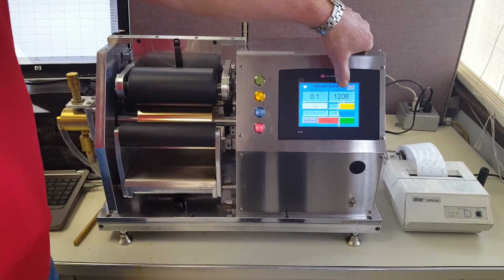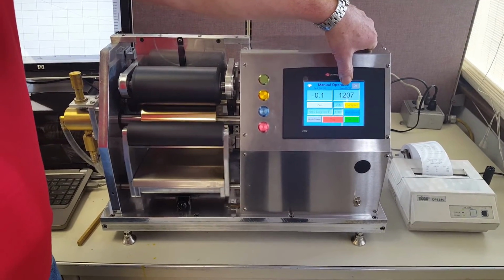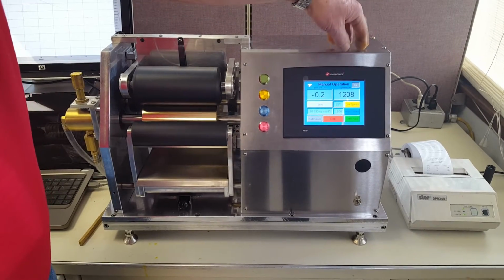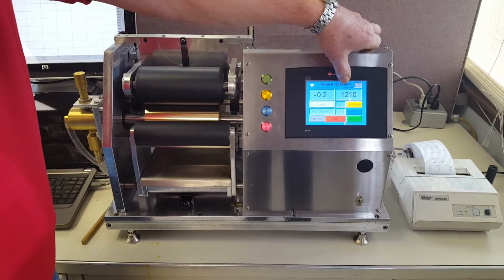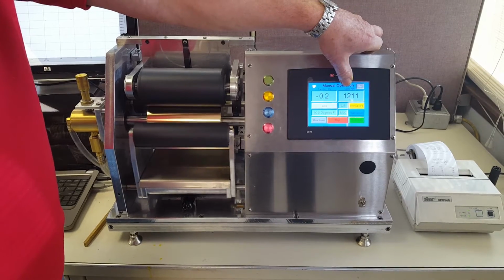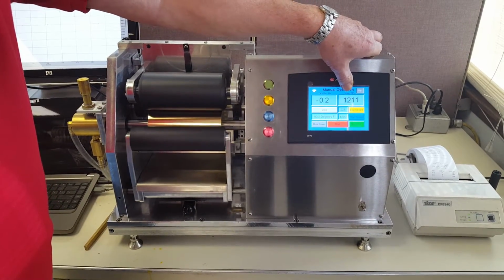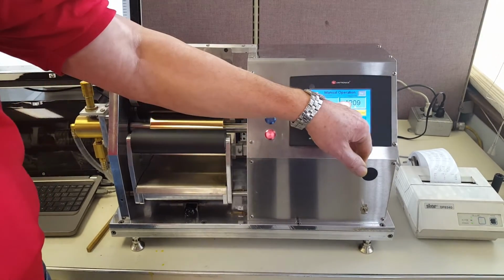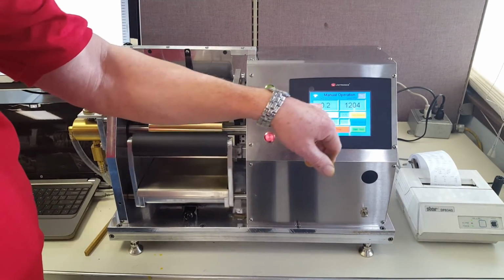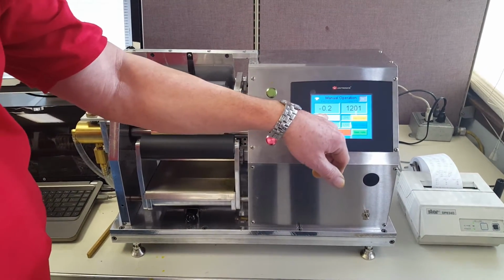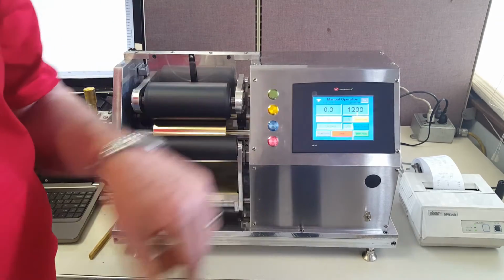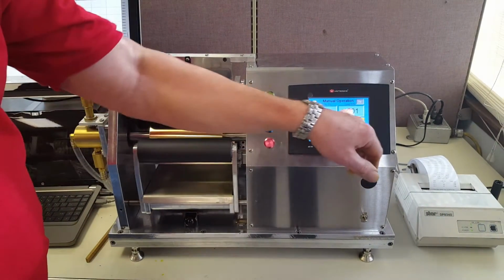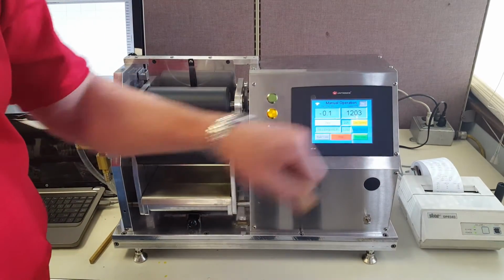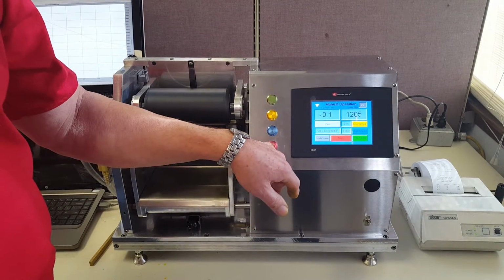Here's our speed over here, hovering right around 1200. This machine can hold the speed within 5 RPMs of our targeted speed, so you'll see it settle in right around 1200. Here's our tack value - we're very close to zero. I'm just going to fine tune that. Our speed's right there at 1200, our tack is at zero, so we're ready to run our test.